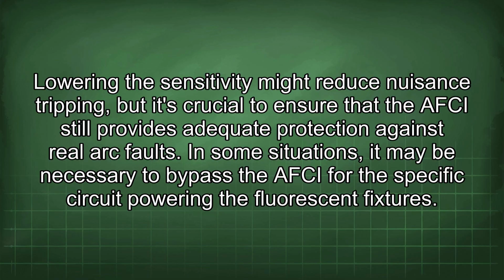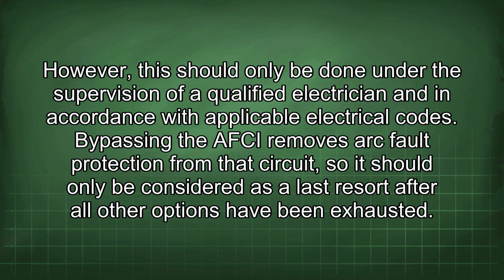In some situations, it may be necessary to bypass the AFCI for the specific circuit powering the fluorescent fixtures. However, this should only be done under the supervision of a qualified electrician and in accordance with applicable electrical codes. Bypassing the AFCI removes arc fault protection from that circuit, so it should only be considered as a last resort after all other options have been exhausted.